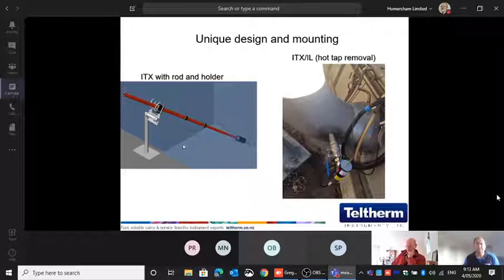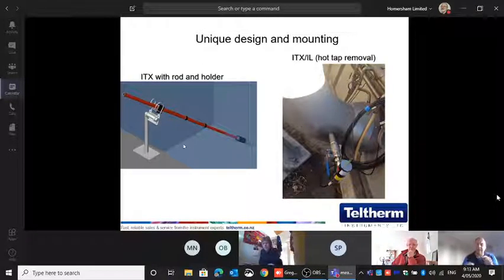What was that comment about black sludge, sorry? Lagoon sludge is very black. The problem that we had with the light is it won't penetrate the sludge to get to the other side, so you can't measure it. The unit basically freaked out every time we saw lagoon sludge. All the other times it was fine, but lagoon sludge is just black. It's like tar. As soon as it came in, you could see it straight away.